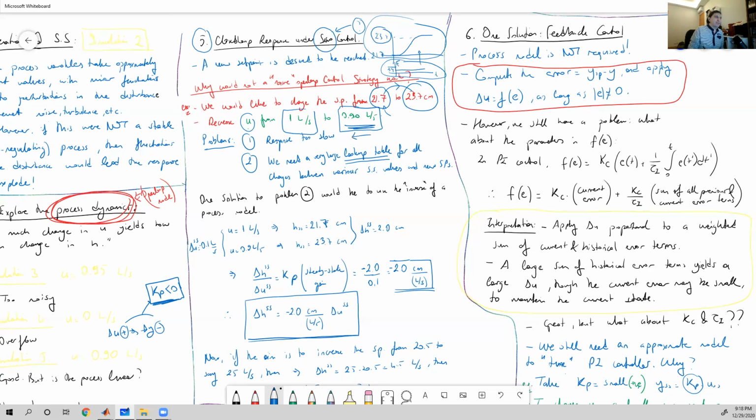Well, we have two problems with that strategy. First of all, if you recall, this response was due to the open loop time constant of the process, which we have found changed from operating point to operating point, but was in the order of about 100 or 150. So reaching the steady state will be somewhat equal to 5 tau values. So this seems to be a pretty large value, maybe up to 500 seconds or maybe 400 seconds. So we have to wait for a couple of minutes to reach that value.